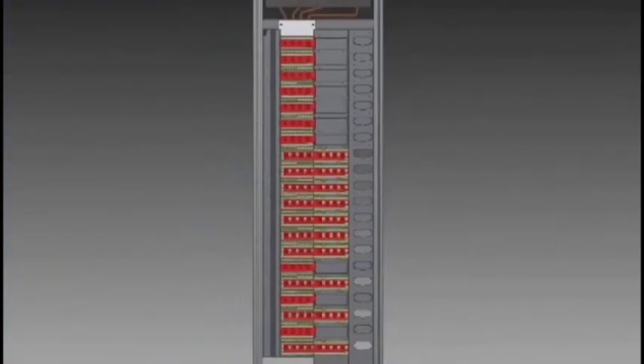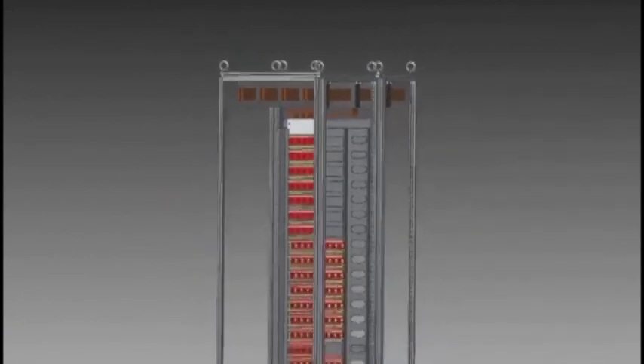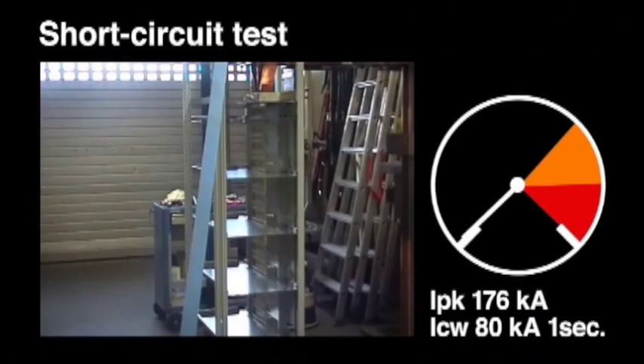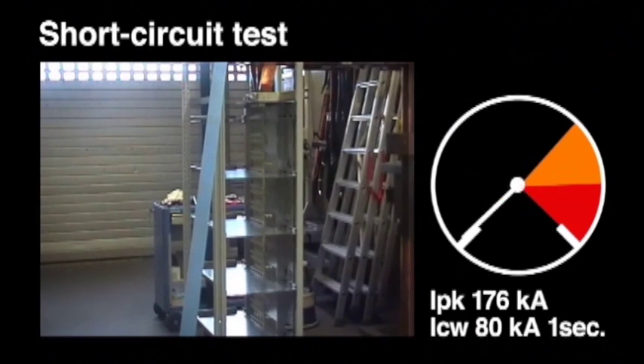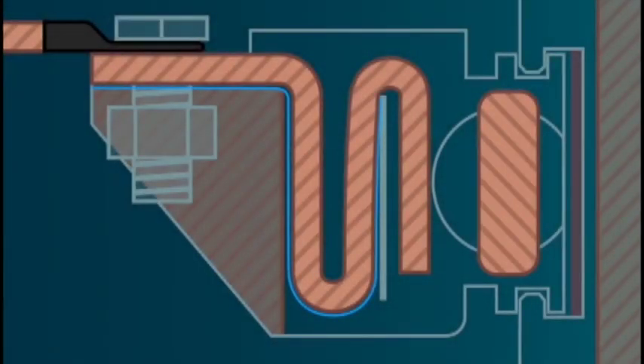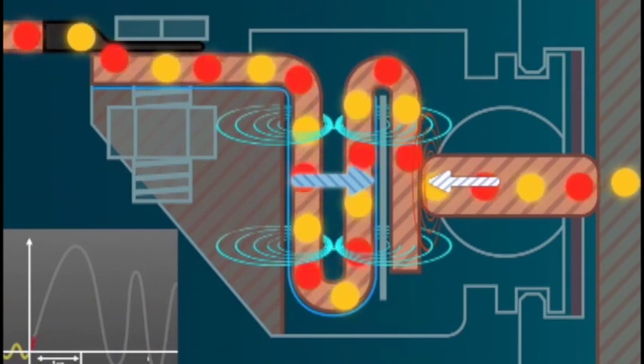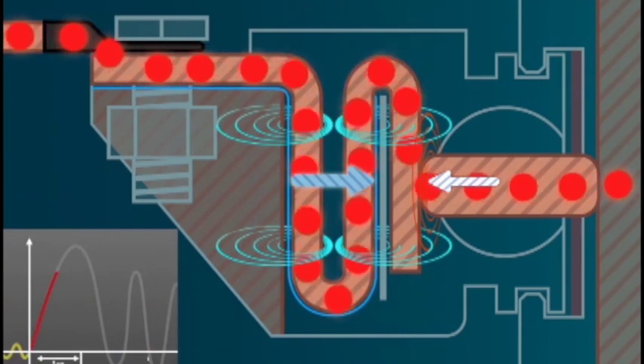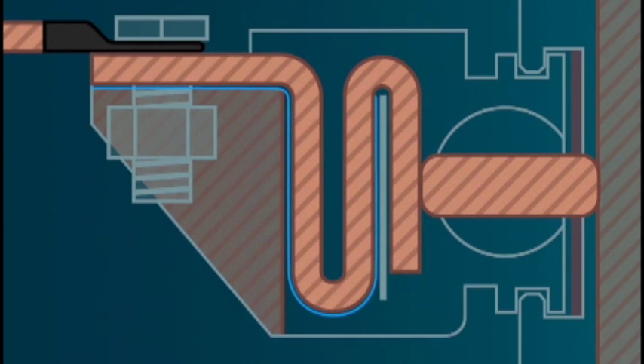There is no infringement of the movement of the vertical bus section to the pressure contact, because the contact can slide horizontally over the surface of the copper bar. Geometry and dimensions of this pressure contact ensure that the magnetic field within the U-shaped conductor generates a higher force than the opposite repulsive contact force caused by the electromagnetic constriction.